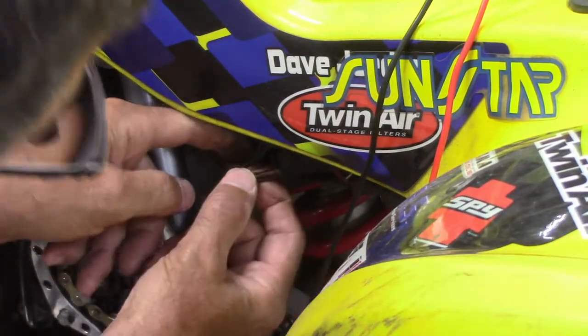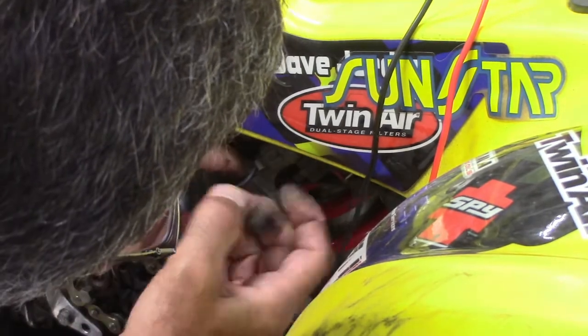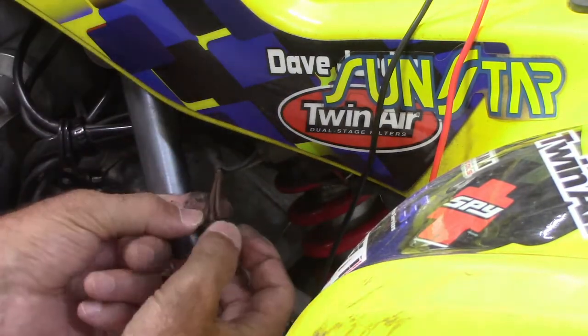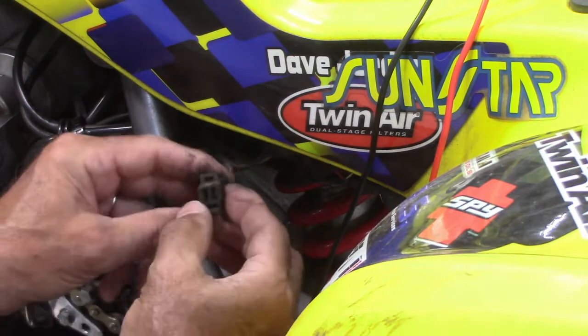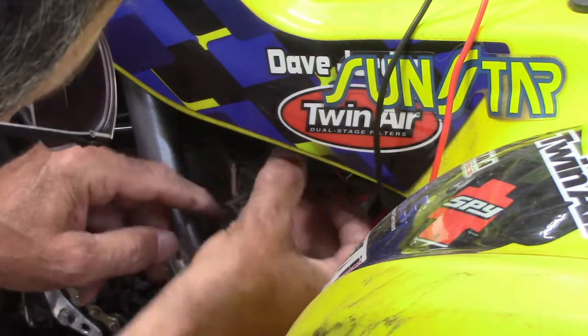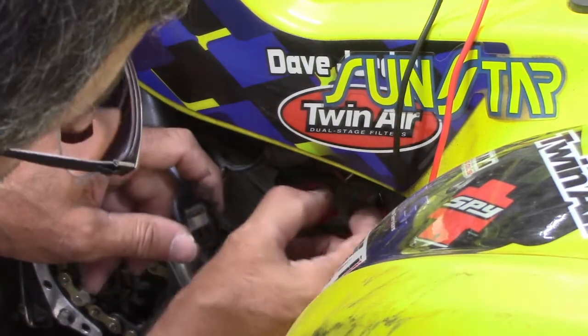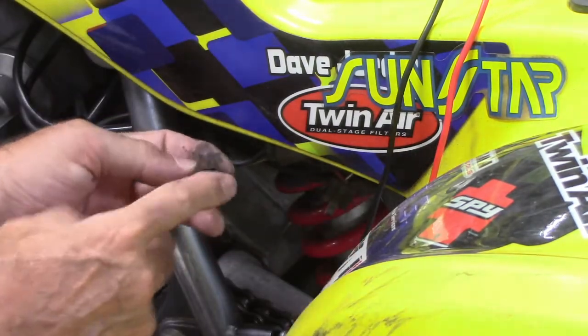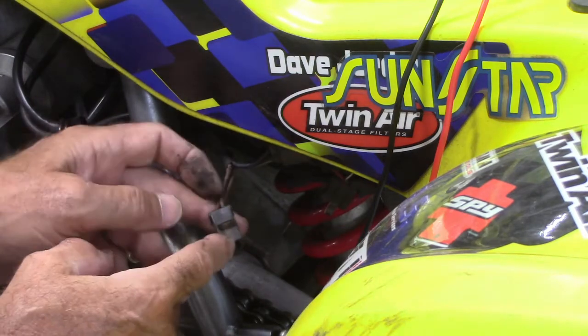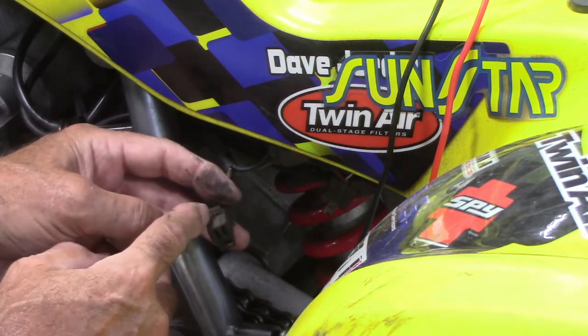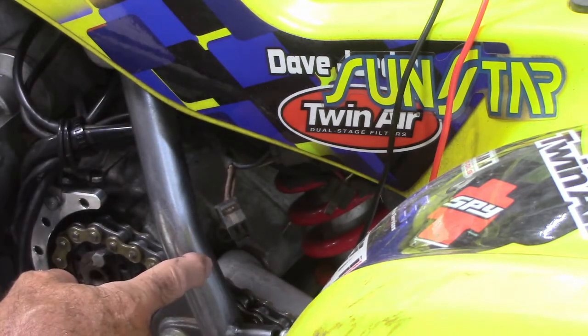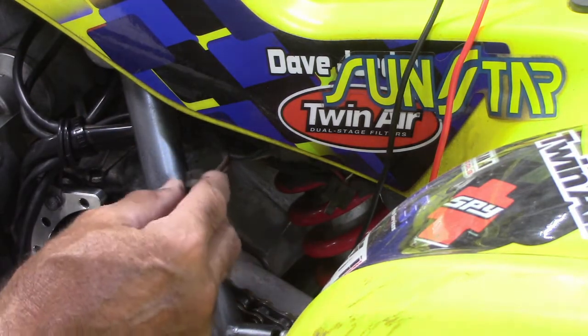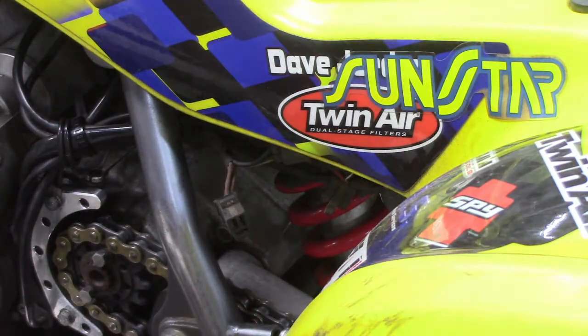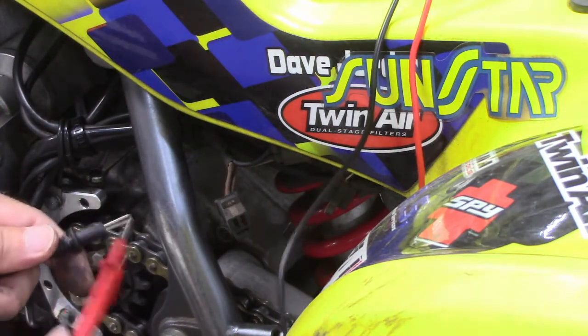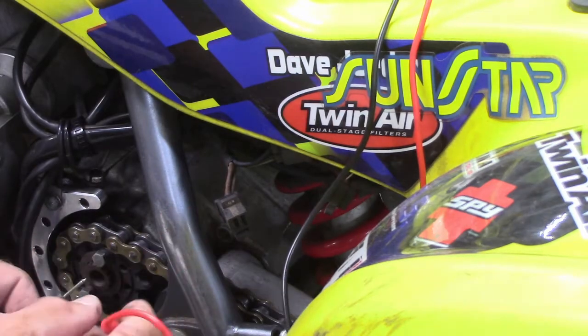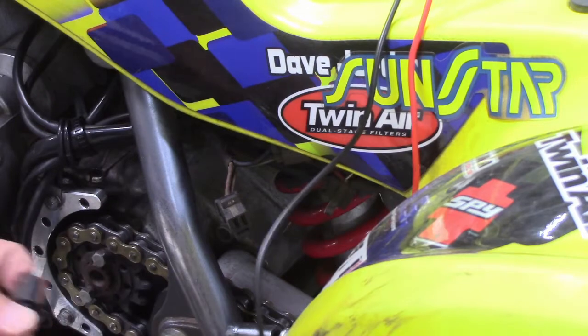Which I believe is this connector right here - it's got 3 brown wires going to it. I want to start here. These wires go to the stator, and I want to make sure none of these wires have continuity to ground. So I'm going to do a continuity test and make sure none of these are grounded - they should not be touching ground anywhere.